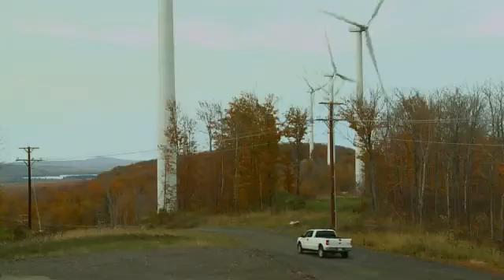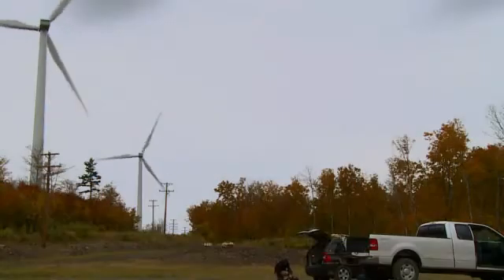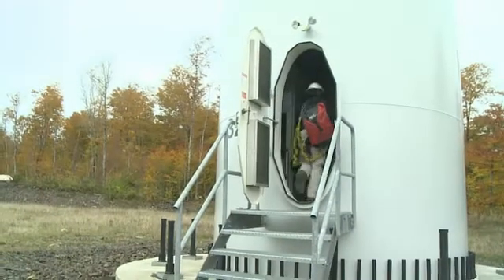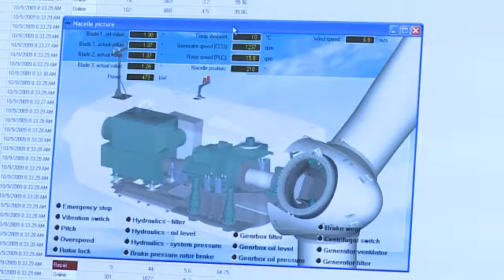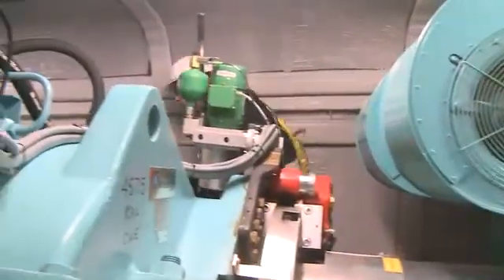On low-wind days, we'll go out and perform turbine inspections. We want to make sure our turbines are going to run as they're designed to run. During our regular turbine inspections, we'll shut the turbine down before we climb, perform lockout-tagout. Then we'll climb the 300-foot ladder, visually checking cables on the way up. Once we get to the top of the tower, we place the turbine into a status where it won't yaw or turn with the wind so that we can safely enter the nacelle.